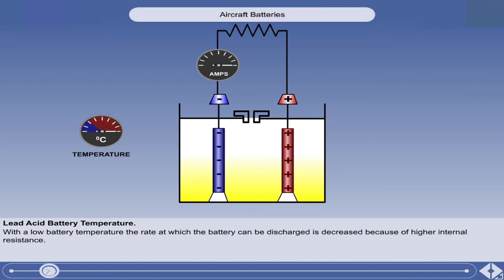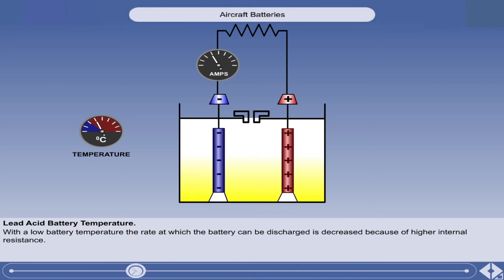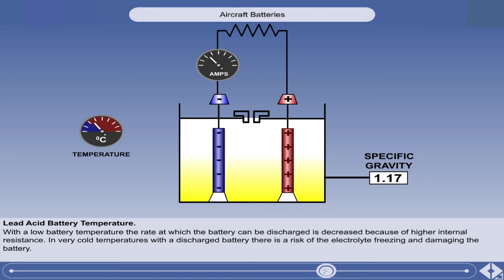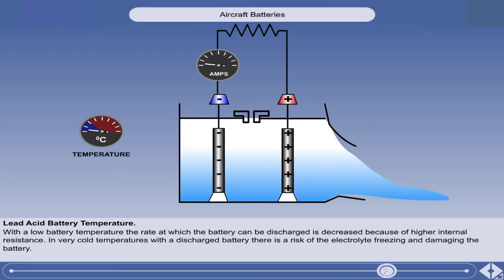The performance of a lead acid battery is affected by its temperature. With a low battery temperature, the rate at which the battery can be discharged is decreased because of higher internal resistance. In general, the battery performs better when it is kept warm. When a lead acid battery discharges, the specific gravity of the electrolyte reduces, which increases the temperature at which the electrolyte will freeze. In very cold temperatures with a discharged battery, there is a risk of the electrolyte freezing and damaging the battery. It is therefore important to maintain the battery in a fully charged state during winter operations.